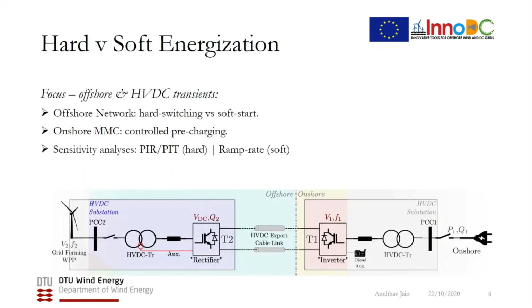Next, we focused on HVDC transients related to offshore network energization: transformer and MMC transients, and onshore MMC precharging from the DC link side. Sensitivity analyses illustrated the impact of a pre-insertion resistor and voltage ramp-up rates on transients during hard switching and soft start of the offshore grid.